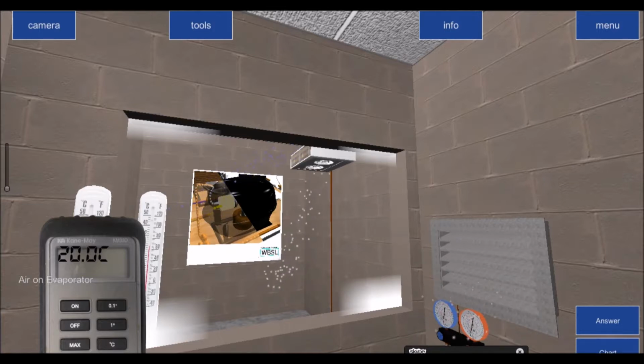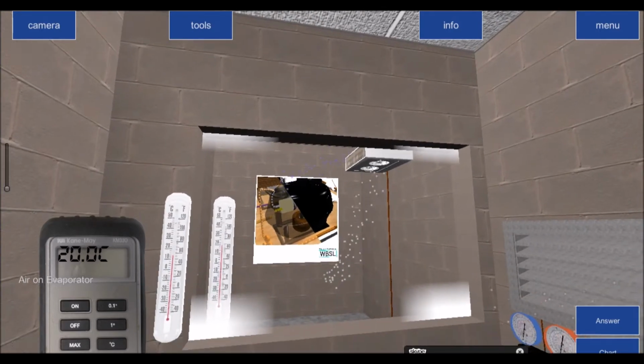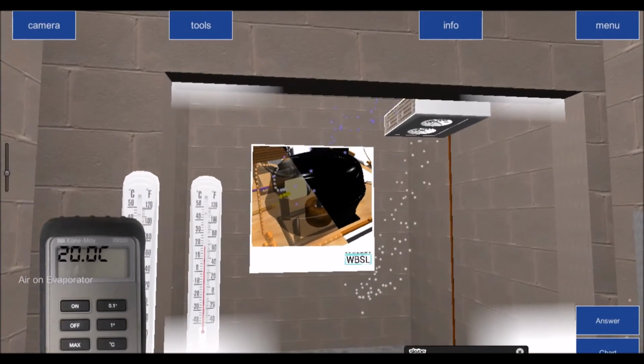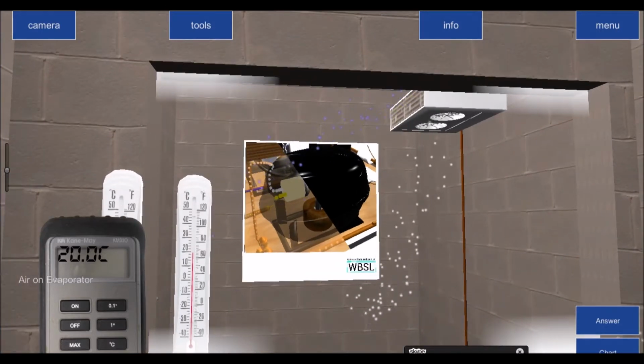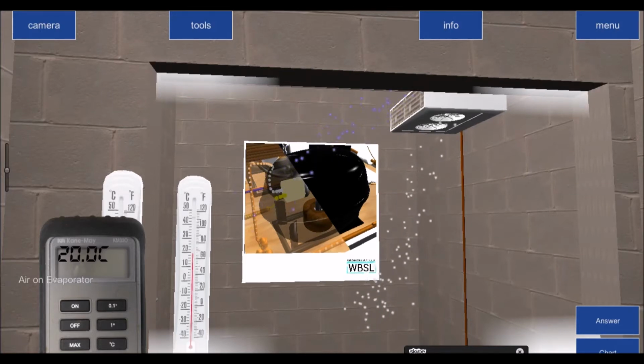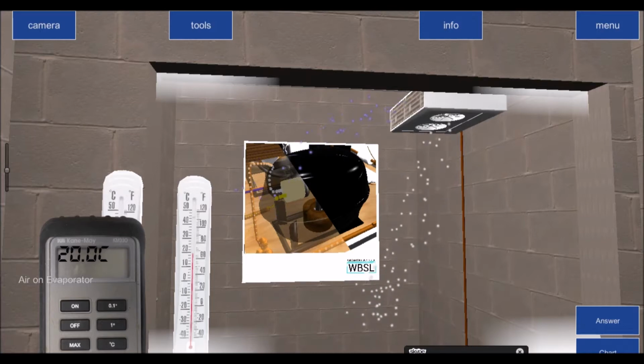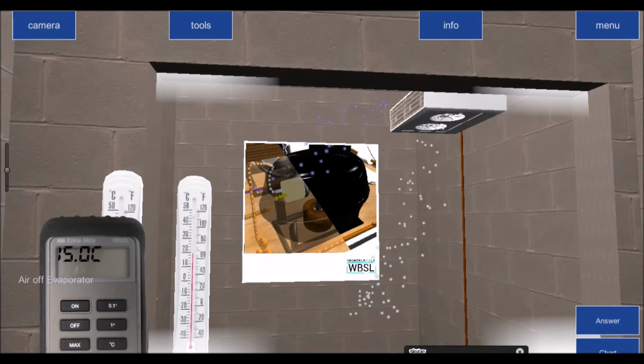So if we look at our room temperature, I'll show you the thermometer inside in the room, in degrees Celsius. We can see that it's 20 degrees Celsius. But you can also see, by me putting my probe to the air on the evaporator, which is the air coming from the room back onto the evaporator, that's the air that contains all the heat that's been removed from the product. That air gives up its heat to the refrigerant, so that's what boils off the liquid refrigerant inside the evaporator. So when the air is coming off, you're going to see it at a lower temperature than it comes on. So there's a temperature difference of air on and air off, okay?